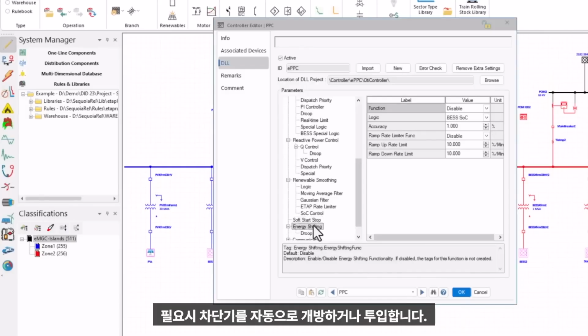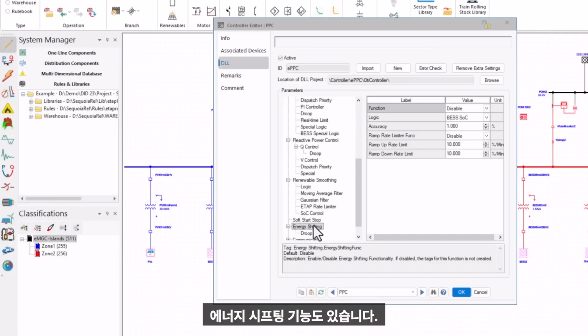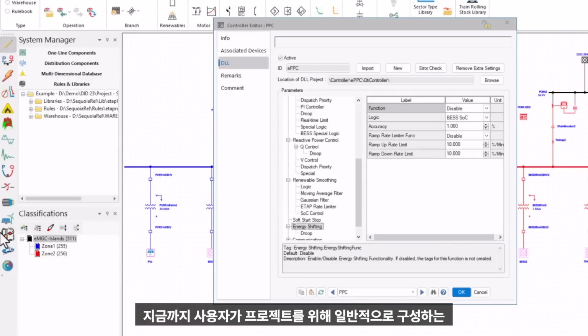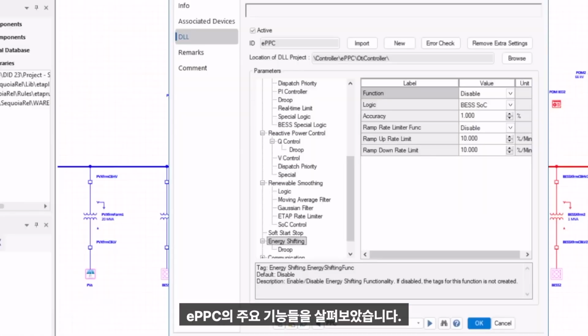We also have energy shifting, which supports energy arbitrage using the BESS. In this mode, the operator provides a schedule that defines when the battery should be charged and when it should be discharged during specific hours of the day. Based on the schedule, the ePPC dispatches the BESS accordingly, allowing the plant to shift energy over time to support operational and economic objectives. These are some of the main ePPC functionalities that users typically configure for a project.